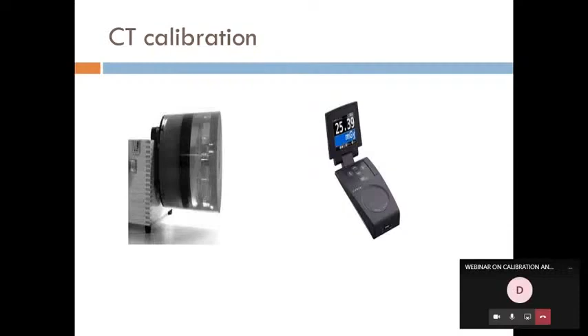This is a typical dosimeter used to calibrate the CT scan. Instead of a patient, you put a dosimeter on the table and take X-rays, and you need to get a value. That value should be the same as the set value. The set value in the CT machine and the observed value in the dosimeter should be the same. If not, you need to check the CT scan.